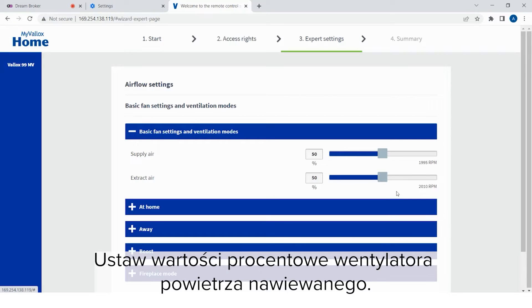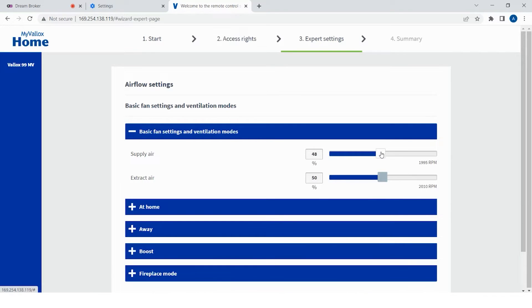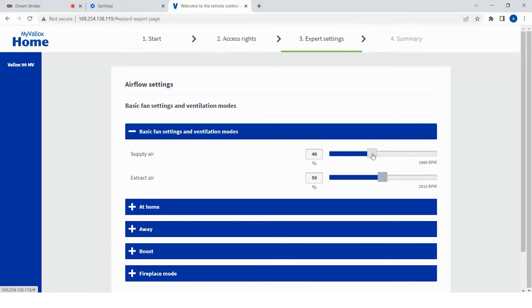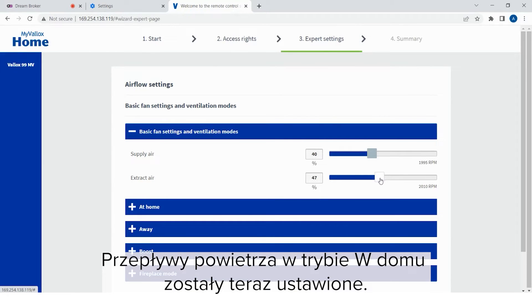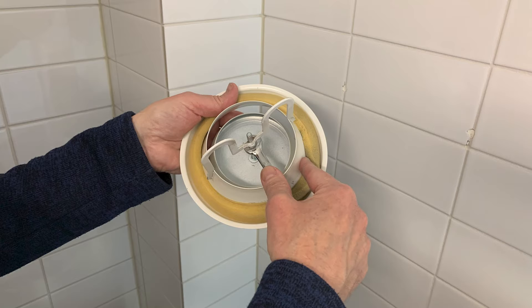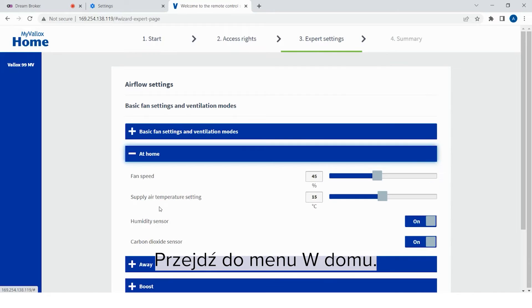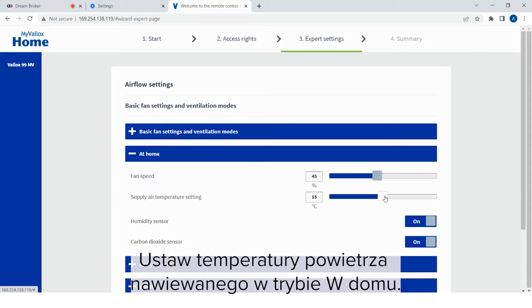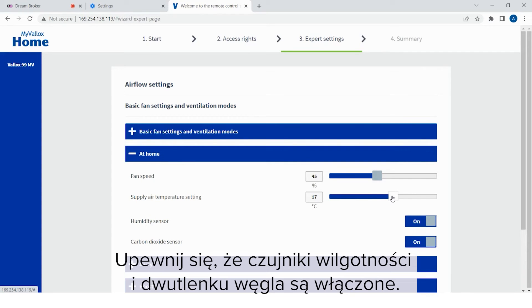Measure the air flows from the supply and extract air valves. Set the percentage of the supply air fan. Set the percentage of the extract air fan. The air flows at the at-home mode have now been adjusted. Lock the valves. Go to the at-home menu. Set the supply air temperature of the at-home mode.